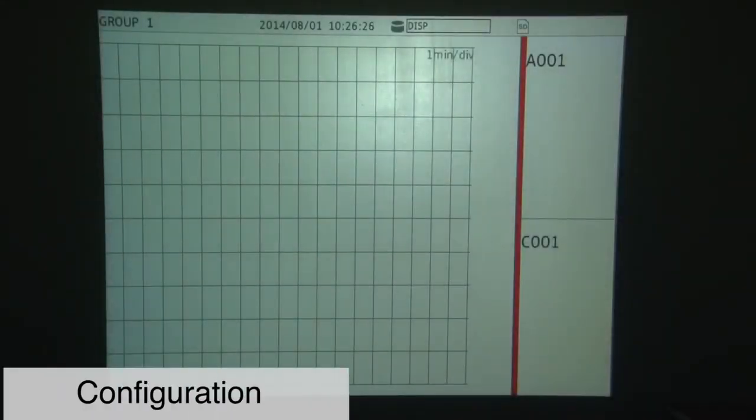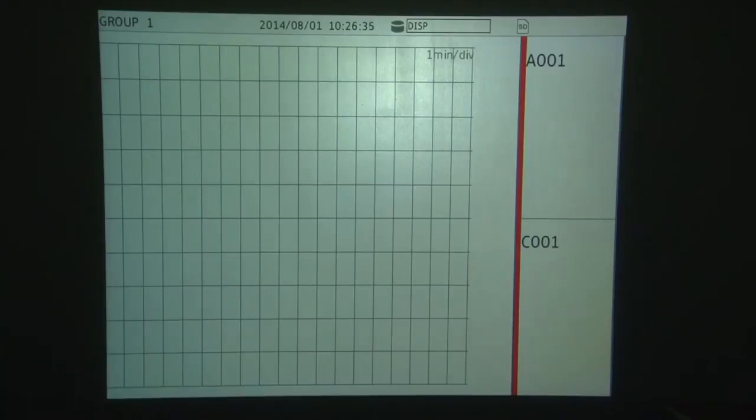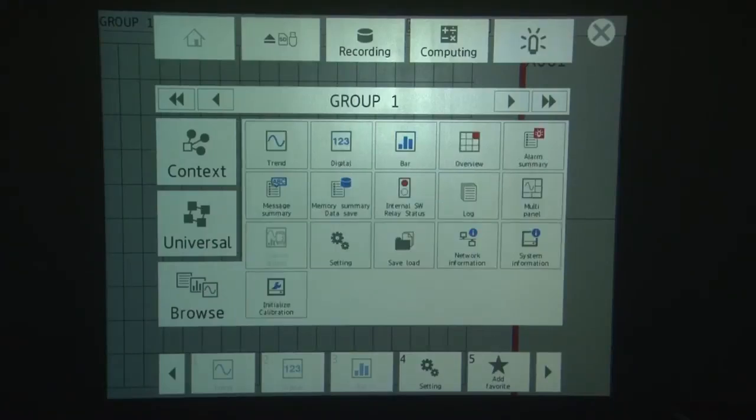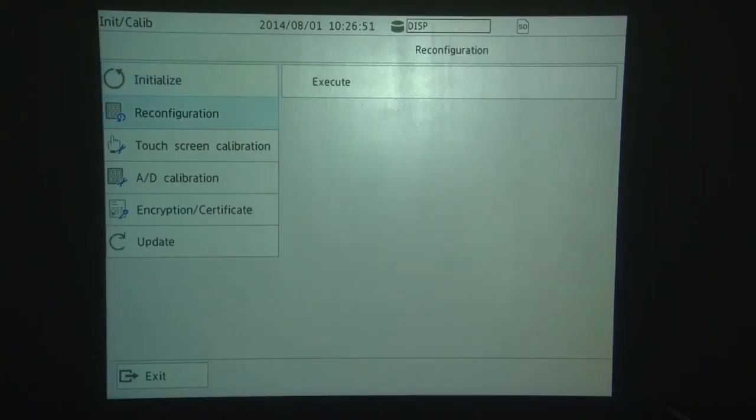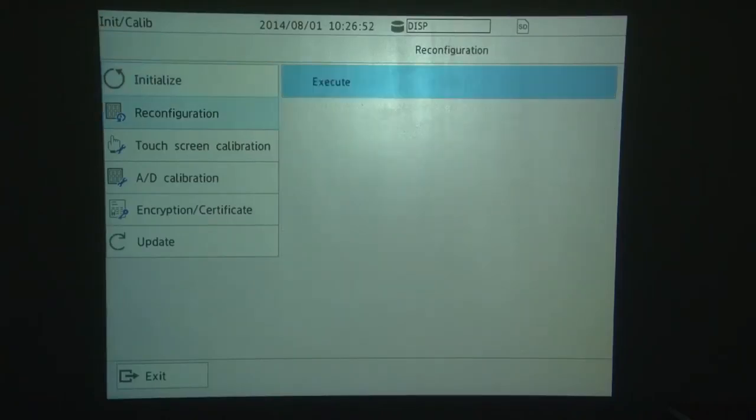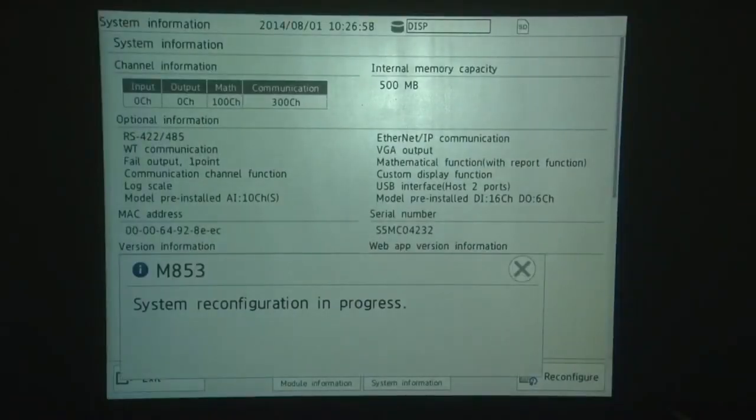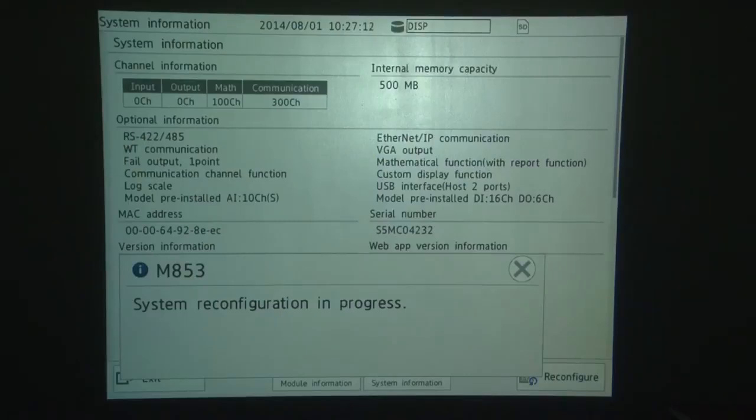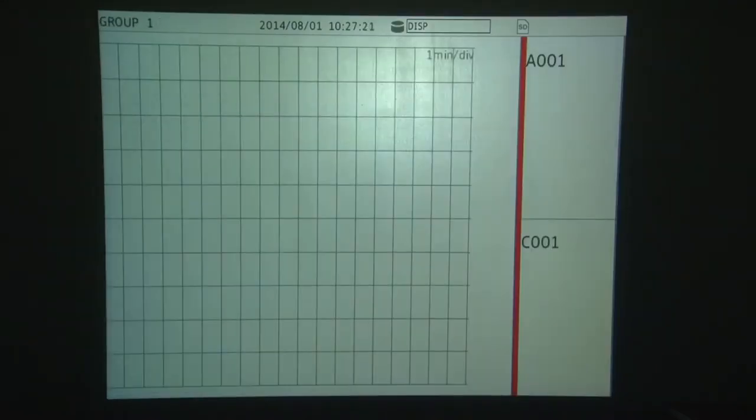Okay, so we've just attached a thermocouple wire to channel A001 on our input module. And we're ready to start our configuration. So the first thing we do is press the blue menu button on the front panel. That's going to take us to the main setting screen for the GX. And we're going to touch Browse. And then we're going to go to Initialize Calibration. And we're going to choose a function called Reconfiguration. So we touch Reconfiguration. And then touch Execute. And then touch Reconfigure in the lower right corner. Click OK. And what this does is the GX is basically taking inventory of the modules on the rear panel. So in about 10 seconds, it's going to go out and look for any attached modules. And then read the settings and configuration from the modules. And it's ready for all the channel settings that it needs. So we're all done. We're going to touch Exit and go back to the main screen.